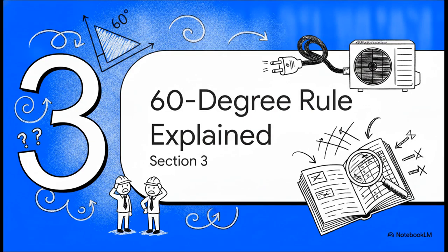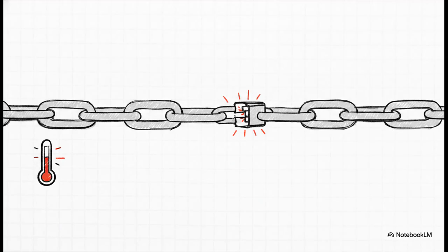Okay, part three, the 60-degree rule explained. Now, what's really interesting about this next part is a common trap that catches so many folks. Here's the trap that trips up a ton of electricians, rookies and veterans alike. We've got our MCA from the nameplate, right? But picking the wire out of the NEC book isn't quite as simple as looking at a single column. Here's why. Even if you're holding premium 90 degrees Celsius rated wire like THHN or THWN2, your conductor ampacity is ultimately limited by the lowest temperature rating of the terminations in the circuit.